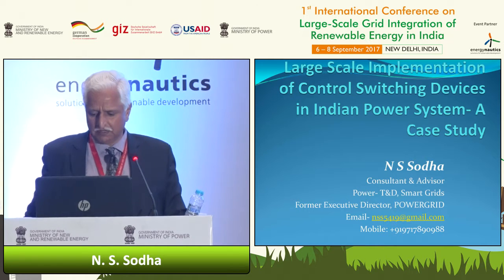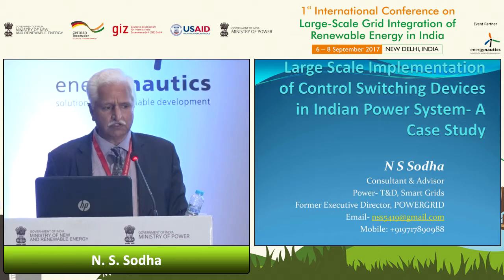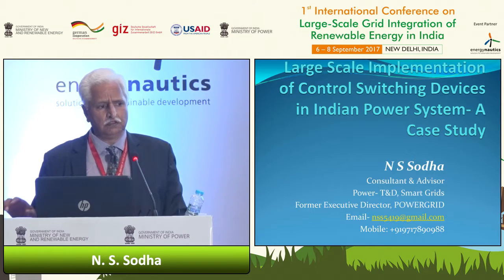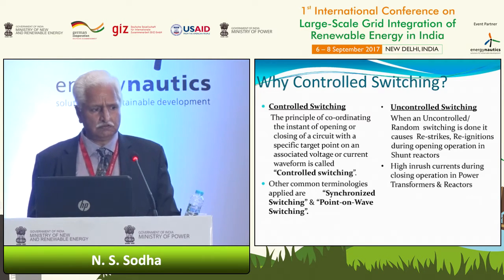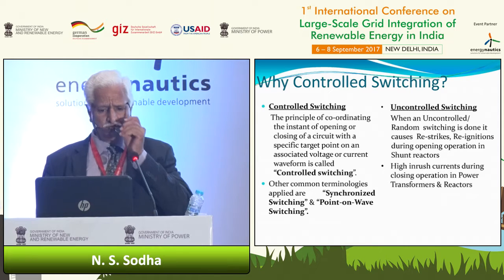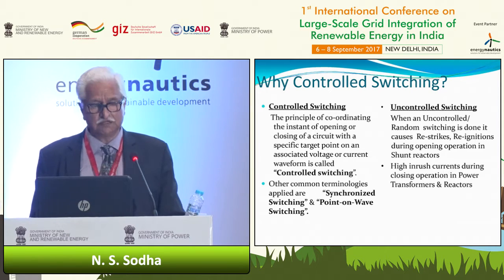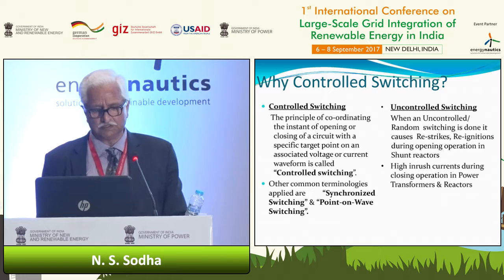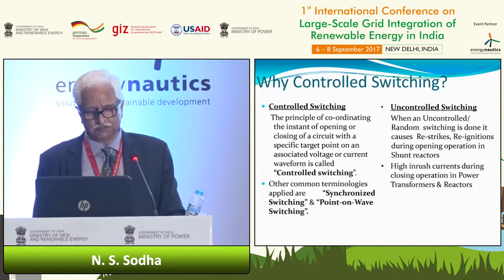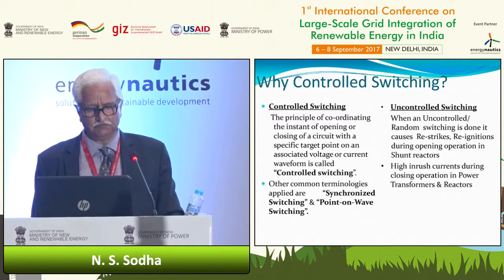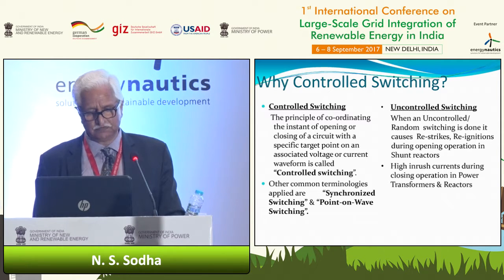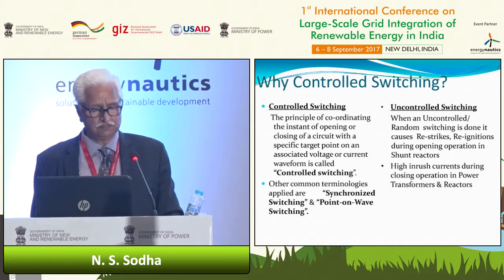the EHV system. And what does control switching mean? Basically, it's the principle of coordinating the instant of opening or closing of the circuit breaker with a specific target point on an associated voltage or current waveform. This is called control switching. Some people call it synchronized switching, and some people call it point-on-wave switching also.